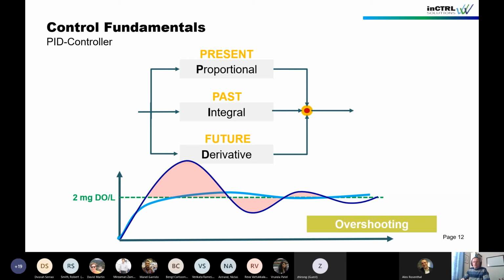In wastewater treatment, be very careful with controllers trying to maintain a fast changing variable. For example, in DO control, the DO signal is changing so fast that the derivative part may amplify the noise you have in that signal. So you have to be very careful.